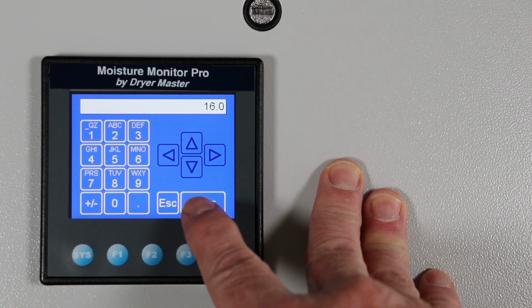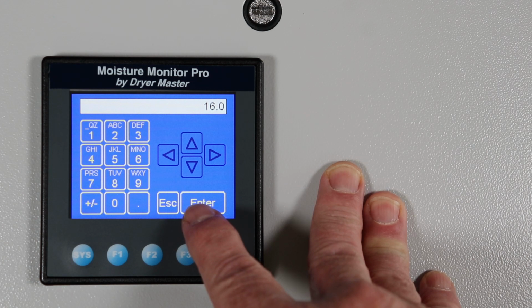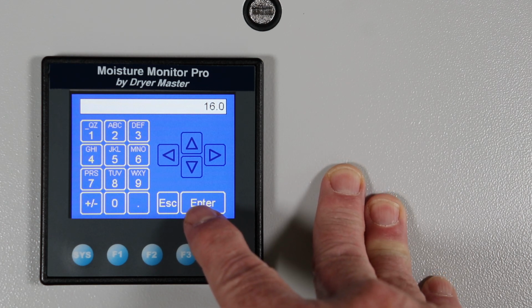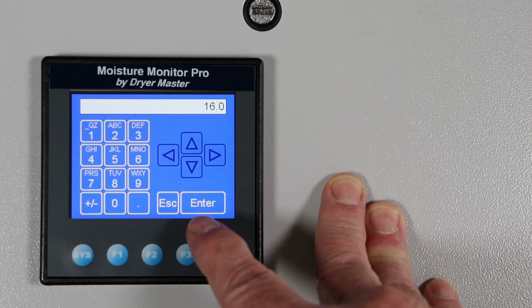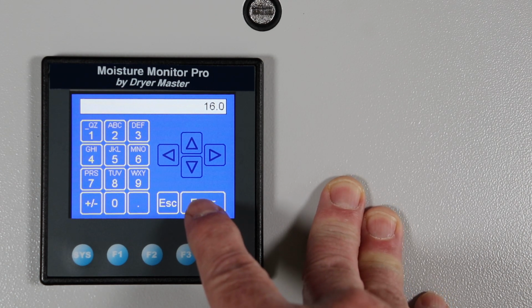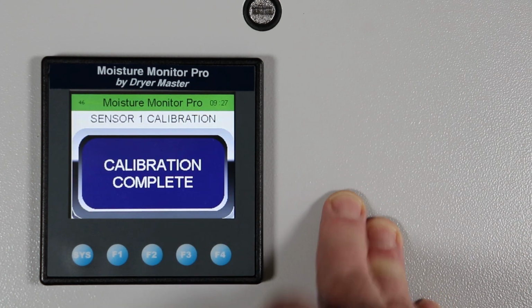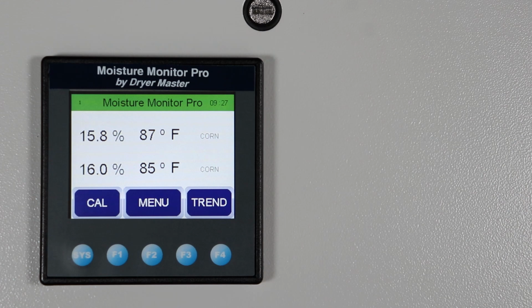Okay, so what's going to happen here is 16 to 15.6. We're going to adjust half the difference. So after we do this, we should see the value of 15.8. So calibration complete. And then we see that the sensor has adjusted to 15.8. Okay, so that's the basics of how calibration works.